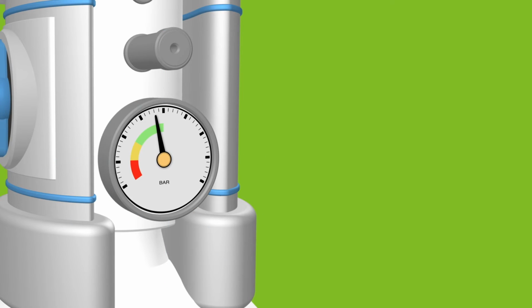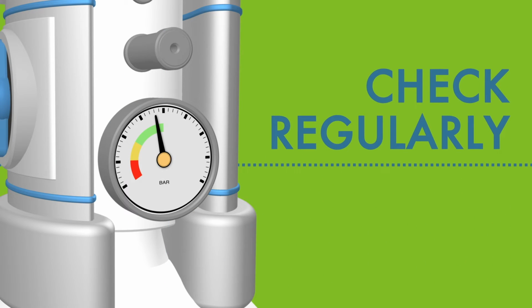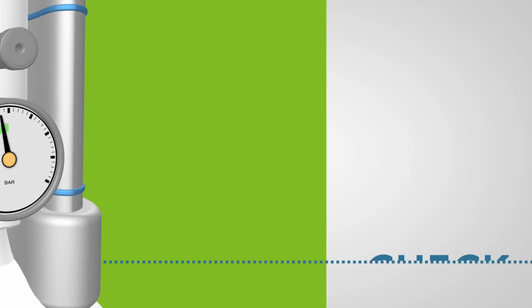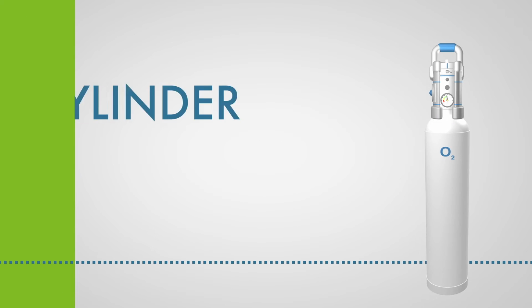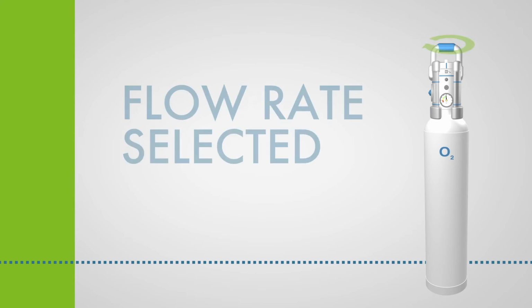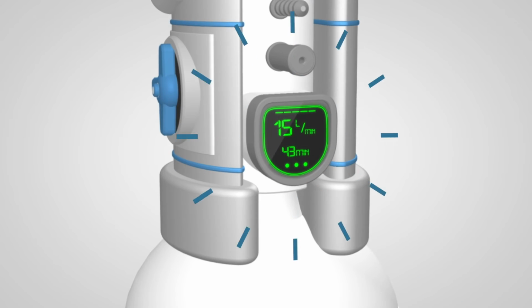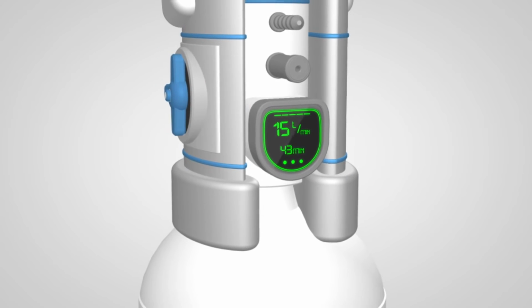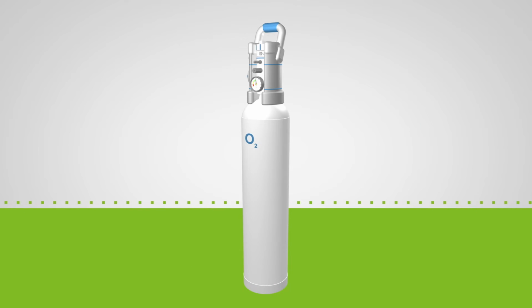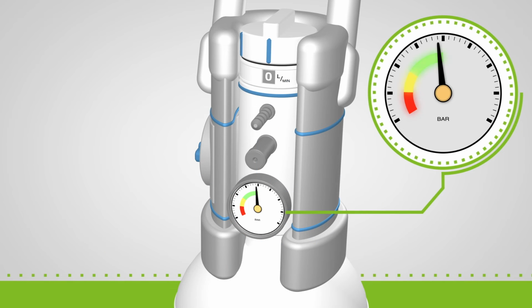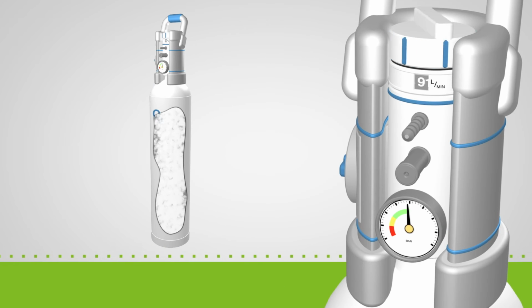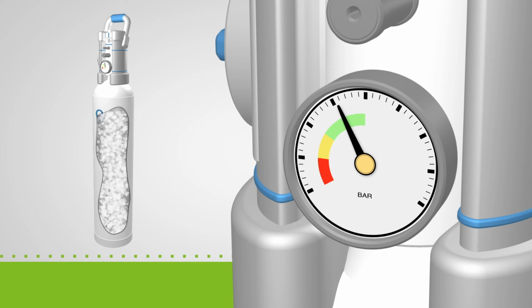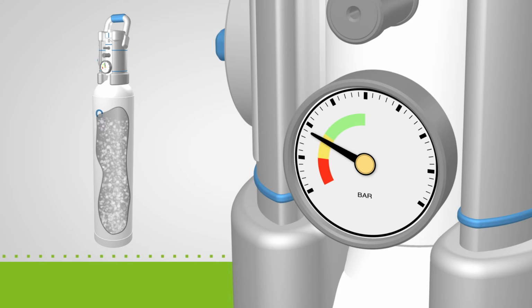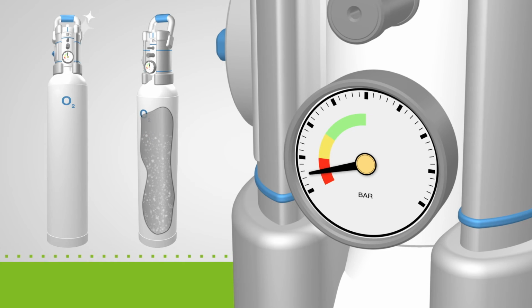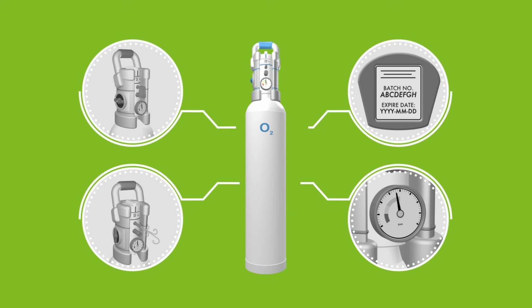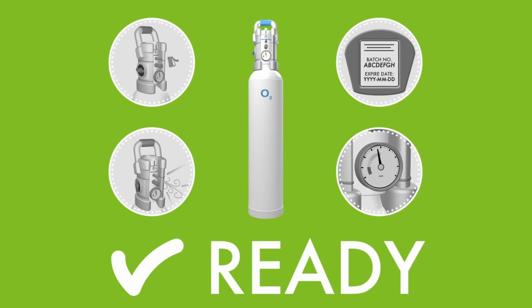The contents gauge needs to be checked regularly to ensure that there is sufficient gas to treat the patient. The frequency of checking will depend on the cylinder size and flow rate selected. If the contents gauge is digital, it will indicate how long the cylinder will last at the set flow rate. If it is fitted with an analog contents gauge, check the colored scale periodically. The greater the flow setting, the sooner the cylinder will empty. As soon as the pointer is in the red section, you need to be prepared to change the cylinder. Make sure that you have a backup cylinder ready before the in-use cylinder is completely empty.